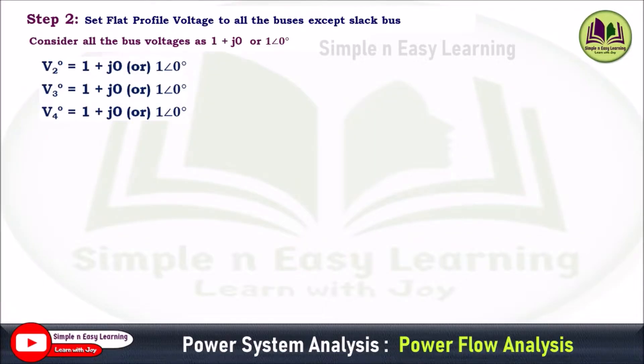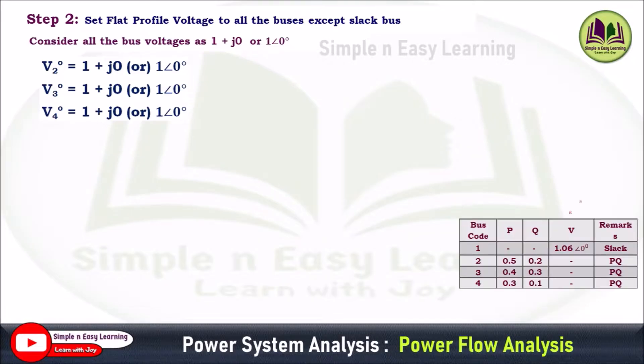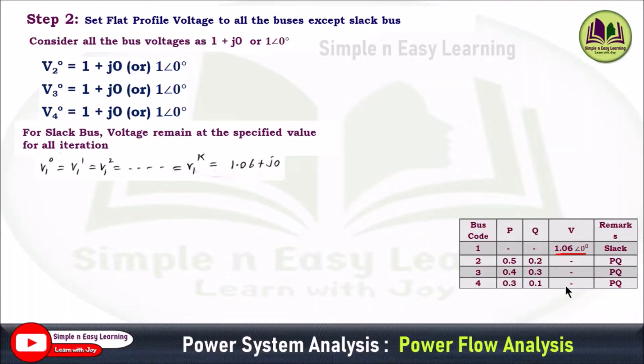V2⁰, V3⁰, and V4⁰ are set to 1∠0° or 1+j0. From the given data, bus 1 is the slack bus — voltage and angle are specified. This value of 1.06∠0° remains constant throughout the problem; whatever the number of iterations, the slack bus voltage remains constant. V1⁰ through V1ᵏ all equal 1.06+j0, where k represents the iteration count. The remaining three buses are PQ (load) buses.